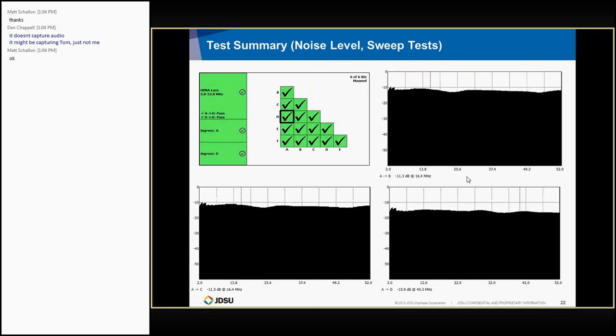Who sets the pass-fail criteria? I'm sure JDSU does the first cut, but do they have the capability to change it, or do they have to ask us to change it for them? They can't change it in the field on the meter. If they want a new set of limits, they could request that we create another file for them, and there is a means to upgrade using the conventional upgrade method that upgrades only the Smartid configuration. So it's a separate configuration file on the unit, not hard-coded. That's correct. But they can't do it themselves. No, not the way we've done it right now.